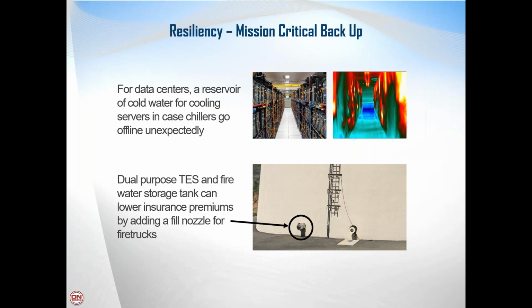And on the resiliency side, on the upper part of this presentation, it's an example of data centers, which include many of our data centers, like Google and Apple and AOL. They have very large data centers with servers inside that are giving off heat all the time, and they need to be cooled all the time. And you can see by the thermal image in the upper right that there's a lot of heat given off by those servers. Well, if their central plant system ever goes down unexpectedly, they have a reservoir of chilled water in their thermal storage tank that could be used immediately for cooling and keeping that data center online. So it's a tremendous benefit for data centers to have that insurance policy and that resiliency of a thermal storage tank in their cooling system.